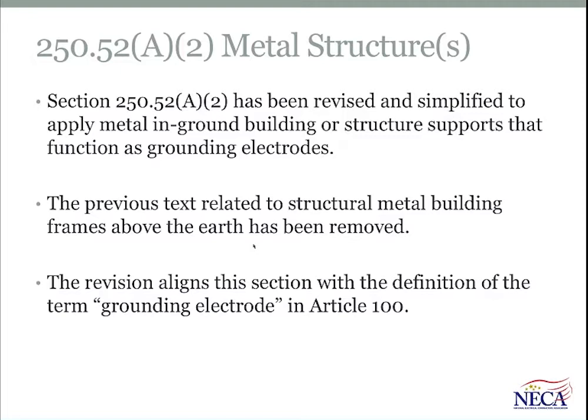So what happens here is the structural metal member that's in contact with the earth is actually the electrode, or the structural metal member that's encased in concrete that's connected to the earth is the electrode. Anything above the earth in the form of a structural metal member is a conductive path to the electrode, and so it acts like a grounding electrode conductor. It's more appropriate that that information from 250.52A2 is relocated to 250.68C. So the whole change here is to not introduce anything new to the NEC, but to align this section with the definition of the term grounding electrode.